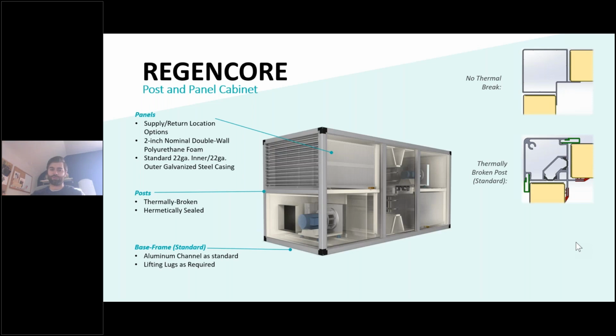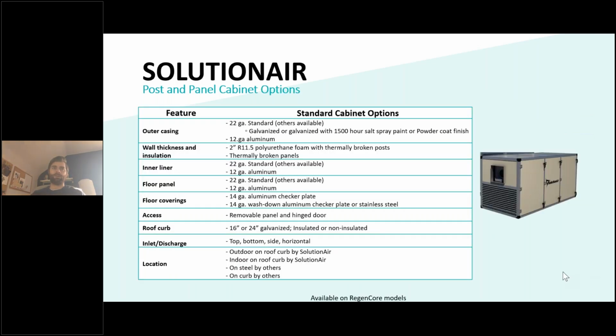We did also test thermally broken panels, but did not find the same importance within those, and found it wasn't very cost effective overall. So thermally broken posts are something I would highly recommend that you make sure your energy recovery unit in this fashion has. Other cabinetry options, so we do 22 gauge inner and outer liner here. As I mentioned, it's 2-inch polyurethane foam injected panels.